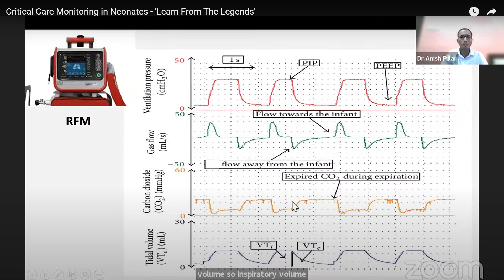And this graph, can anybody type in the comments what has happened? So you can see that the gas flow has stopped. No flow towards the infant, no flow away from the infant, and expired CO2 is constantly being shown. Tidal volume, expiratory can't be detected. Inspiratory tidal volume is there. So this is an ET obstruction.